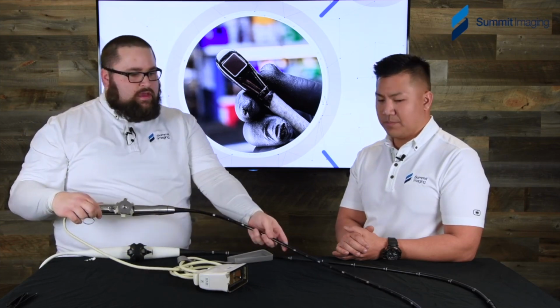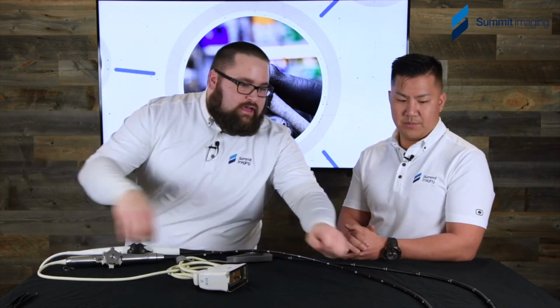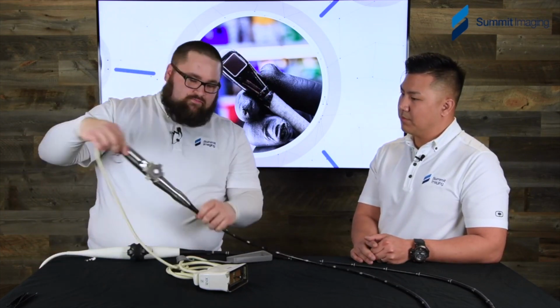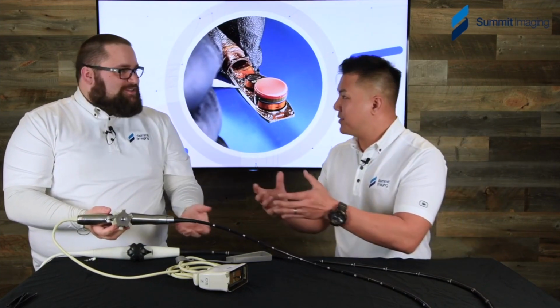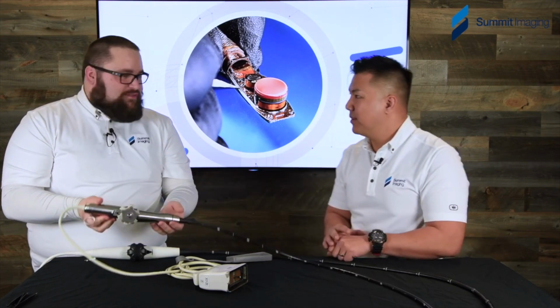There's a high-level rinse-off that just happens in a sink, where they're going to remove any sort of matter that built up, and that's usually the first opportunity for this handle to just get pulled into the sink with the rest of the transducer. Okay? They're trying to get the tip. They're down there. They're scrubbing away, and this is sitting up on the sink and just falls in. They grab it with their hand. They put it back. And their hand is wet. Their hand's soapy. Wet. It's catching it. It's now full of water.